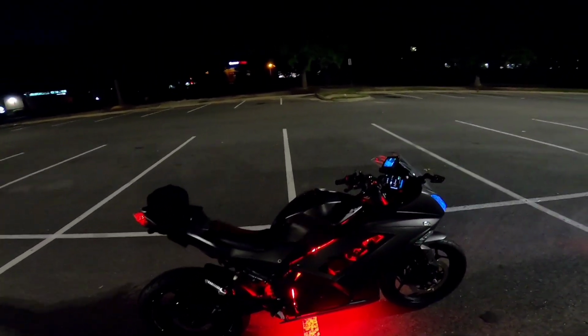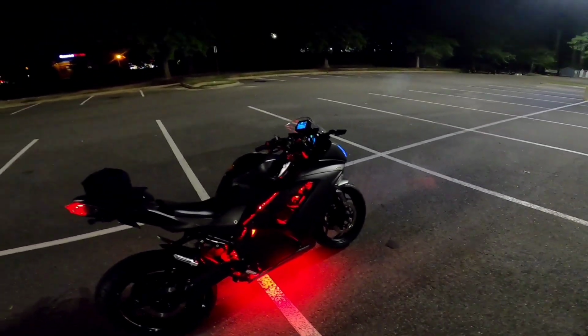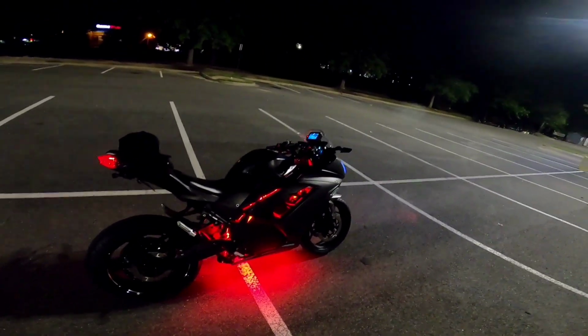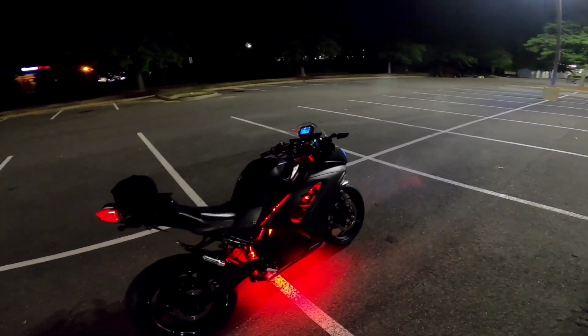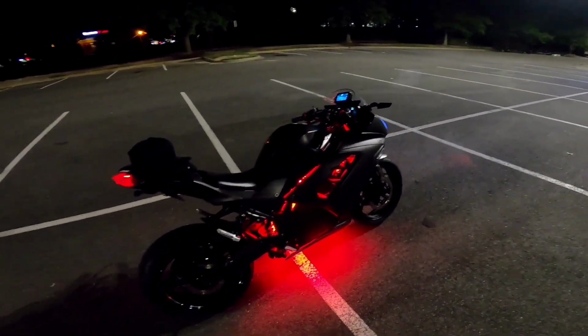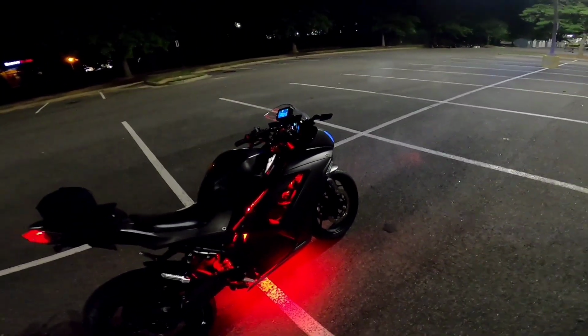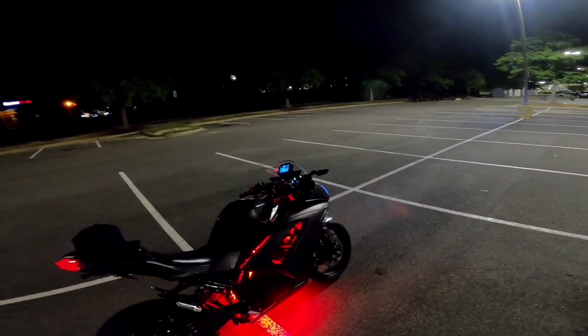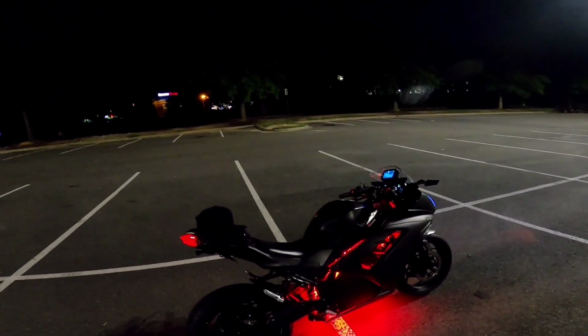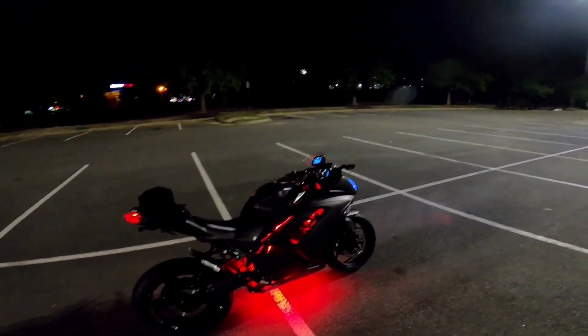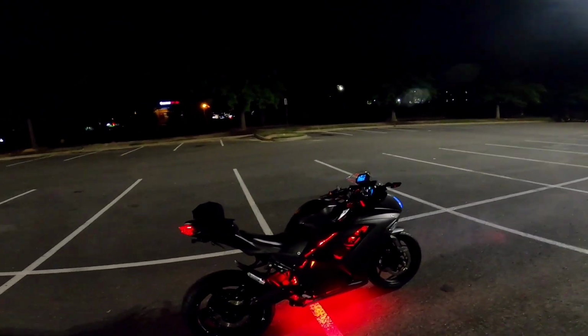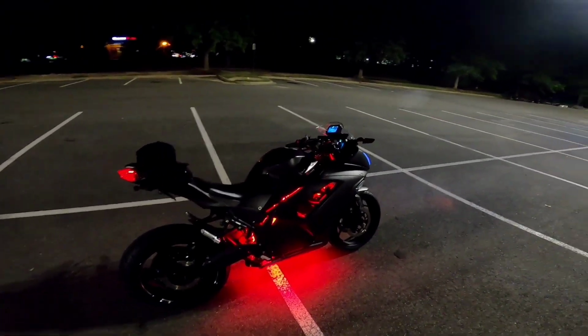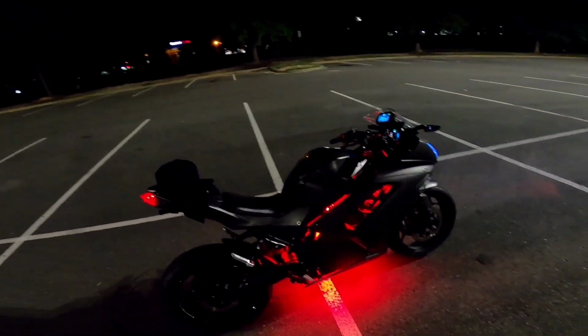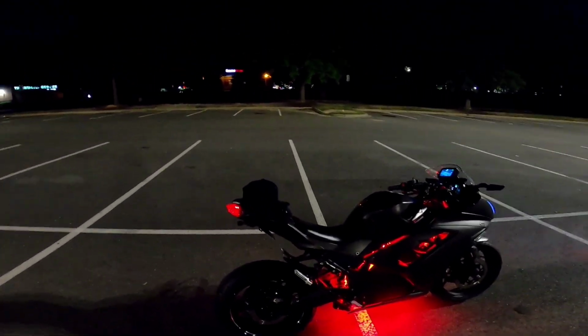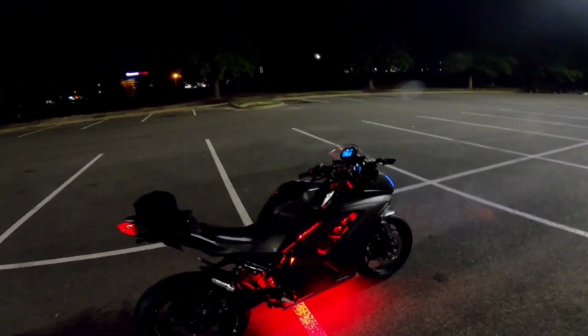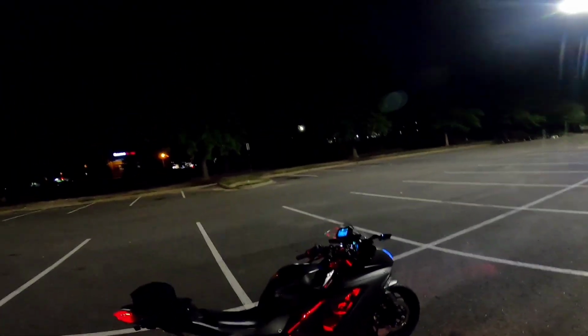Sure, you can get the highest discharge cell, the most capacity cell, and because they say it has 60 amps of discharge peak or 100 amps, you start doing the math and say, well if I got 10P that's 600 amps. True, those 10 cells can probably produce a burst of 600 amps, possibly, but they're damn sure not going to be able to sustain it, nor produce it with the voltage above nominal, which is the main thing.